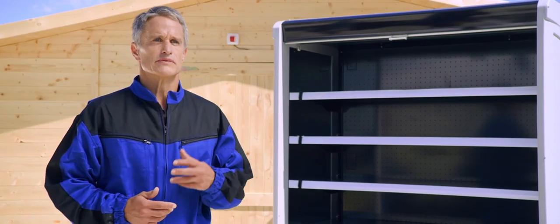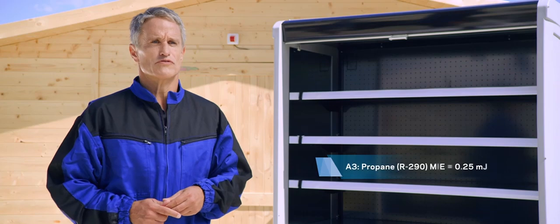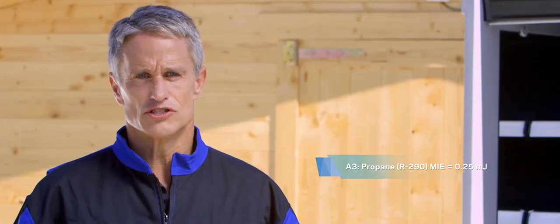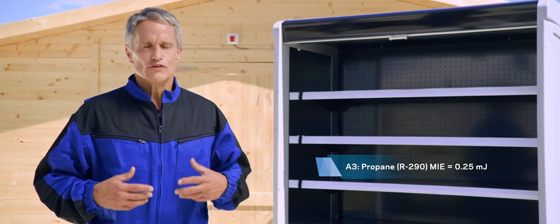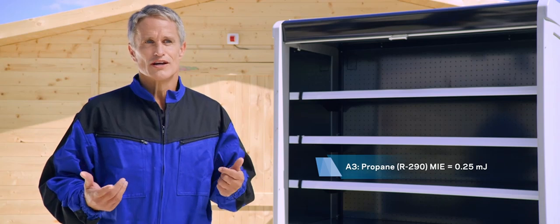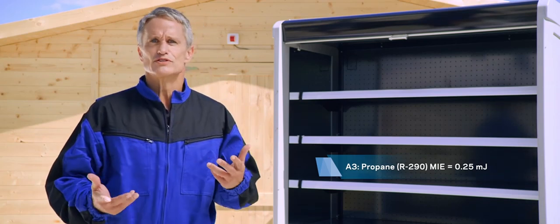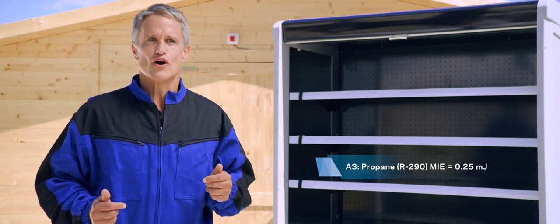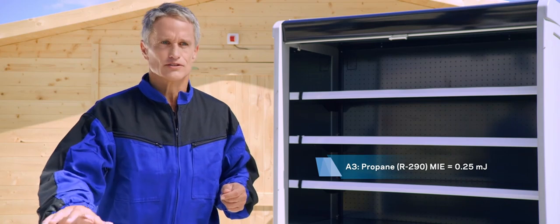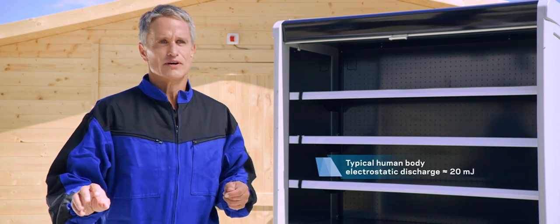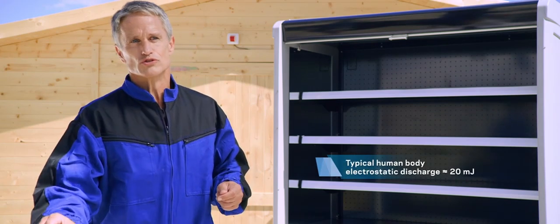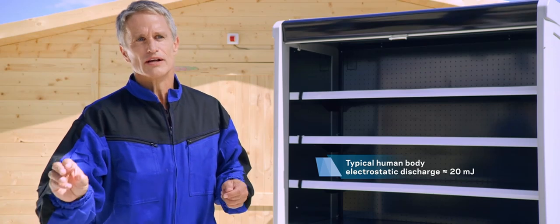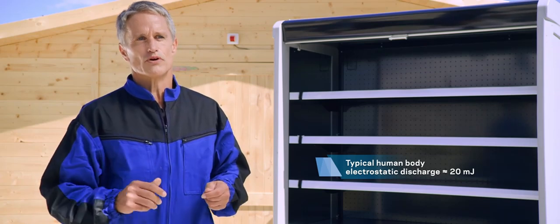Propane has a minimum ignition energy of just 0.25 millijoules, which means that even a weak discharge, say static discharge from your clothing, can exceed this value and potentially cause an ignition event. To give you an idea of what millijoules are, say for example in the wintertime I'm shuffling my feet on the carpet and I touch a door handle and shock myself, that value is 20 millijoules, or almost 100 times higher than the energy necessary to ignite propane.